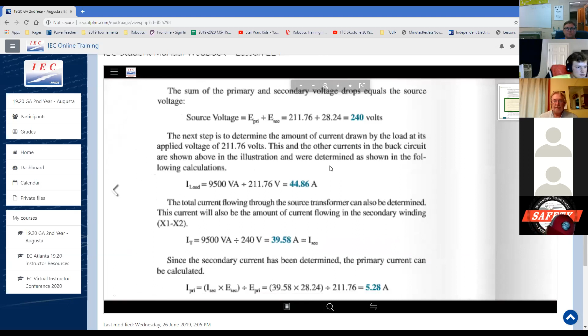All right. So now let's check the load and see if everything's good. We take the 9,500 volt amps and divide that by the 211.76 we got back up here, right? Got it right here. All right, and we get 44.86 amps. That lets us know this and the other currents in the buck circuit are shown here.